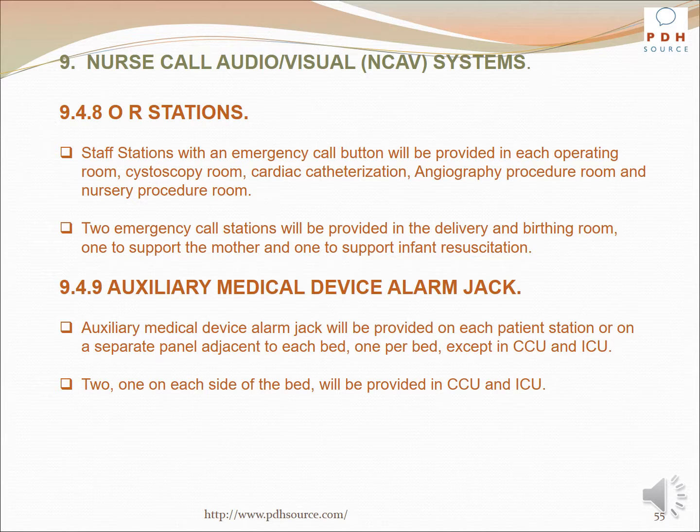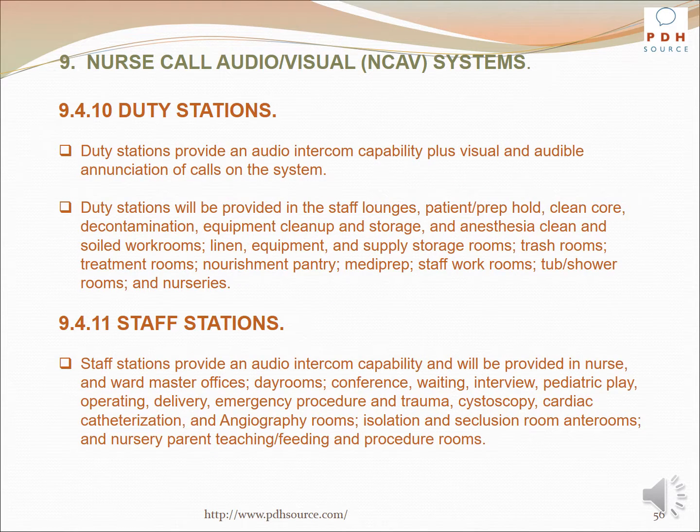Auxiliary medical device alarm jack will be provided on each patient station or on a separate panel adjacent to each bed, 1 per bed, except in CCU and ICU. 2, 1 on each side of the bed, will be provided at CCU and ICU. Duty stations provide an audio intercom capability plus visual and audible enunciation of calls on the system.